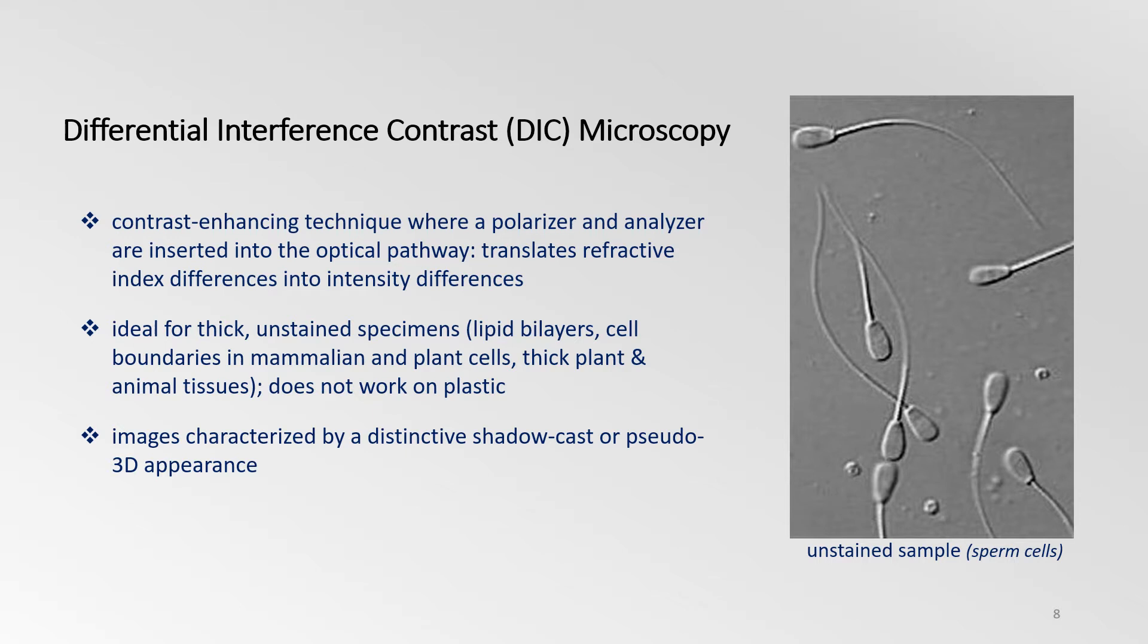Differential interference contrast, or DIC microscopy, is another brightfield method used to enhance the contrast of transmitted light images. It uses the polarization of light, translating refractive index differences into changes in intensity. This method is ideal for thick, unstained samples on glass slides or carriers that are not made of plastic. DIC images give the impression of topography and have a distinctive shadow cast or pseudo-3D appearance.